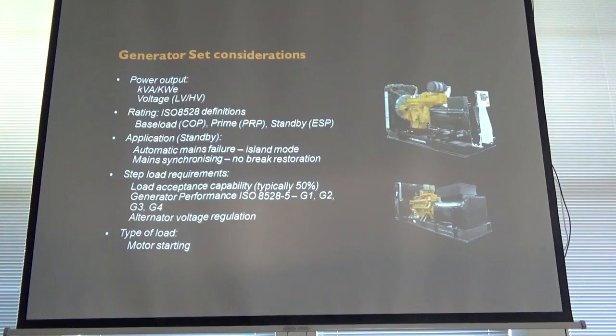Okay? Just now, going back to the car, is this why we normally oversize the generator by something like 30% to 50%? Okay, why would you do that? Is that consideration to future demand? No, for the load. Ah, that's the key thing. Load step requirements. It's very much a question of what equipment you're supporting and its tolerance to the voltage and frequency limits. You know, what tolerance it can accept. If it's an MRI scanner, you've got very tight tolerances of performance. But normally, for instance, the G2 or the G tolerances are very important as well, and they're in section 5 of ISO 8528. They give you the voltage and frequency tolerances, and I'd always default to G2 unless sensitivity of the equipment dictates otherwise. Because if you've got, say, let's just pick some numbers.